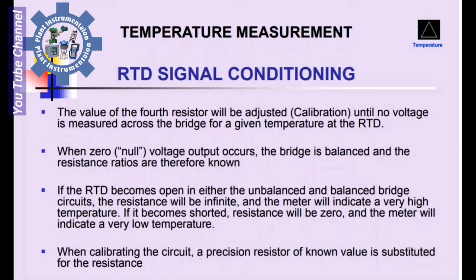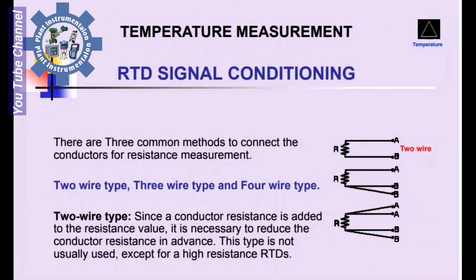If the RTD becomes open in either the unbalanced or balanced bridge circuits, the resistance will be infinity and the meter will indicate a very high temperature. If it becomes shorted, the resistance will be zero and the meter will indicate a very low temperature. When calibrating the circuit, a precision resistance of known value is substituted for the RTD.